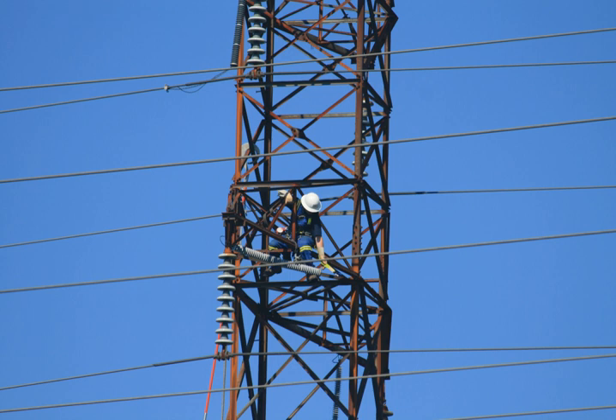In telegraphy and telephony, a lightning arrestor is placed where wires enter a structure, preventing damage to electronic instruments within and ensuring the safety of individuals near them. Smaller versions of lightning arrestors, also called surge protectors, are devices that are connected between each electrical conductor in power and communications systems and the earth. These prevent the flow of the normal power or signal currents to ground, but provide a path over which high-voltage lightning current flows, bypassing the connected equipment.